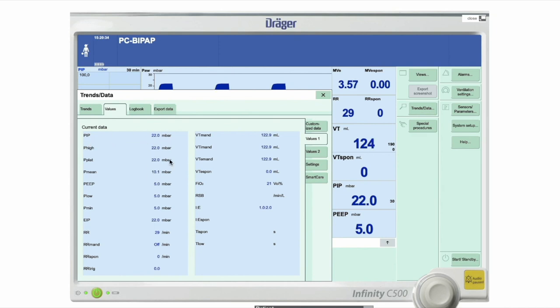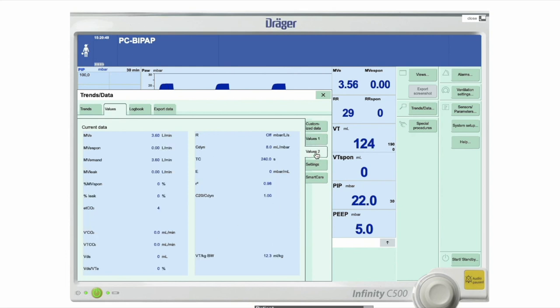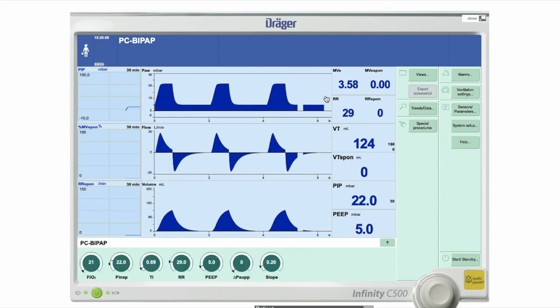So this is what your PEEP is, what your plateau pressure is. This is what your low pressure is. This is what your mandatory respiratory rate is. The number of spontaneous breaths. And then you can go down to the next tab. So therefore you've got more information here. So this is your minute volume leak. This is your minute volume. So all that information is available. You just need to know where to look for it.